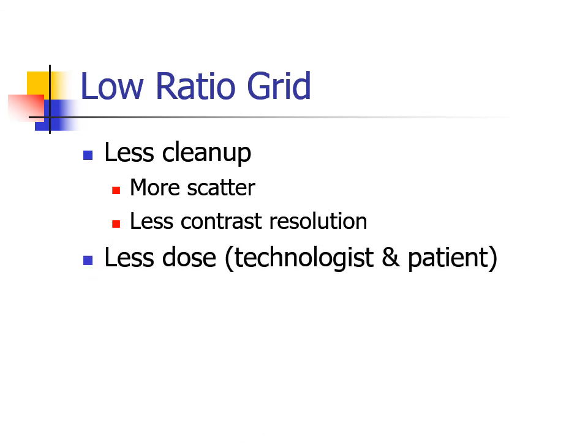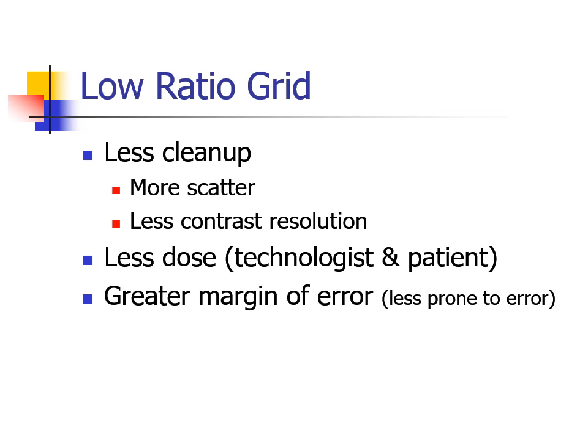As one might expect, the low-ratio grid has the opposite characteristics of the high-ratio grid. More scatter will make it through a low-ratio grid, so the ability of the grid to produce images with high-contrast resolution will be reduced. The compensation factors for low-ratio grids are less, so patient dose will be reduced compared to high-ratio grids. Low-ratio grids can better tolerate misalignment of the central ray, so are well-suited for portable and non-bucky imaging. I'd recommend these grids not exceed an 8-to-1 ratio.